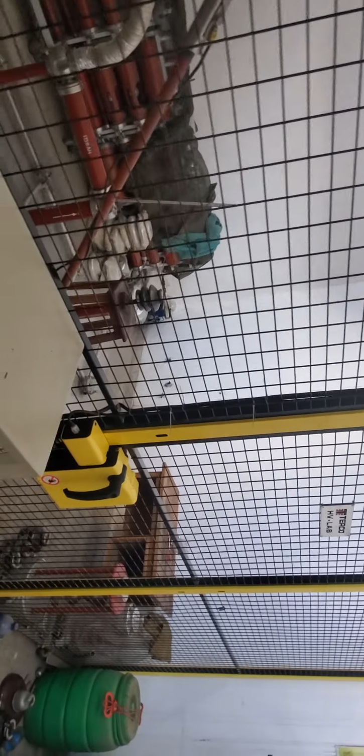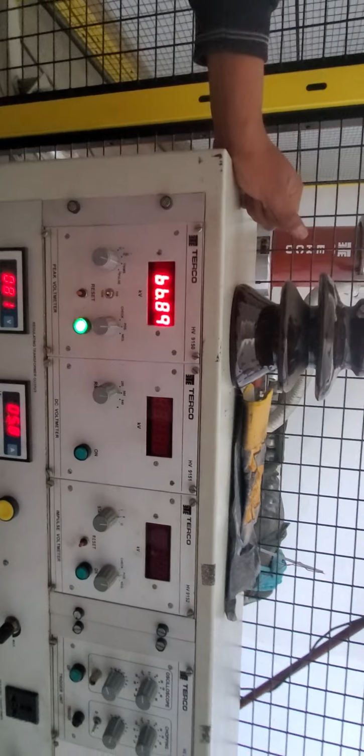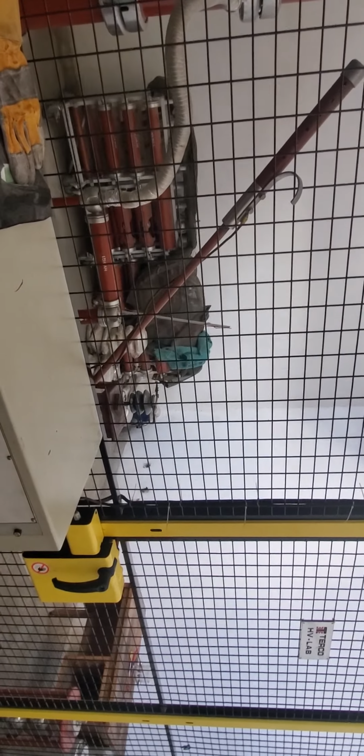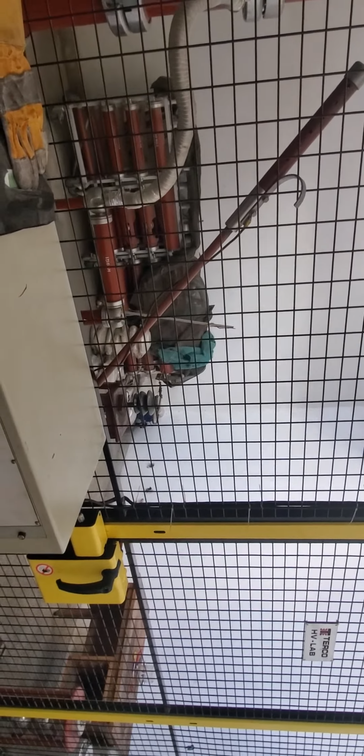So this is flashover, breakdown of air around the conductor. If you observe the flashover, it will occur from phase to what? Neutral. This is your neutral, the breakdown direct from phase. The red wire is phase, the yellow is what? The neutral. So the flashover will occur from phase to neutral. So this is flashover. So we are at what? 65 or 66 kilovolts.